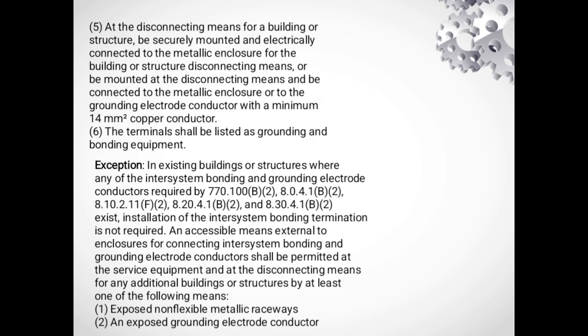An accessible means external to enclosures for connecting inter-system bonding and grounding electrode conductors shall be permitted at the service equipment and at the disconnecting means for any additional building or structures by at least one of the following means. Number 1. Exposed non-flexible metallic raceway. Number 2. An exposed grounding electrode conductor. The IBT must be accessible and have sufficient terminal capacity for all required conductors. It must also be securely mounted and connected to the service equipment enclosure.